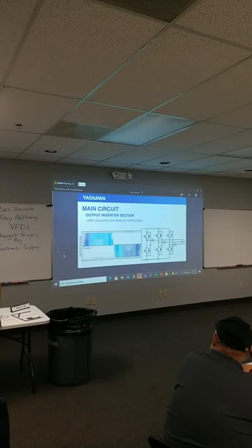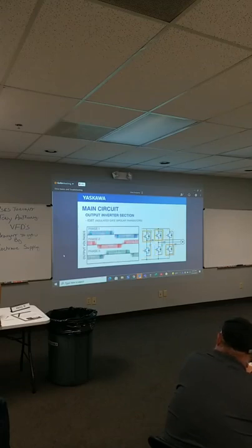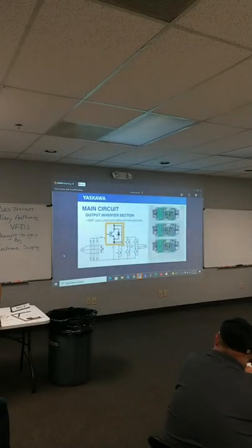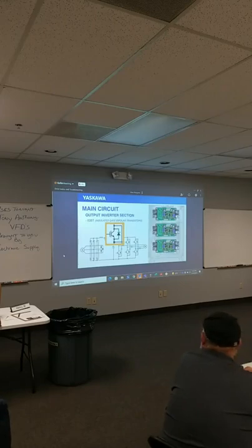Then another IGBT builds the lower half of the wave. Now remember, we have a three-phase motor. So typically, three IGBTs are on at a given time to generate simulated AC voltage waveforms to the motor. These IGBTs have built-in diodes that allow current to flow in the opposite direction of the current flowing through the IGBTs, as may be encountered when turning the IGBTs off or when exposed to regenerative conditions.